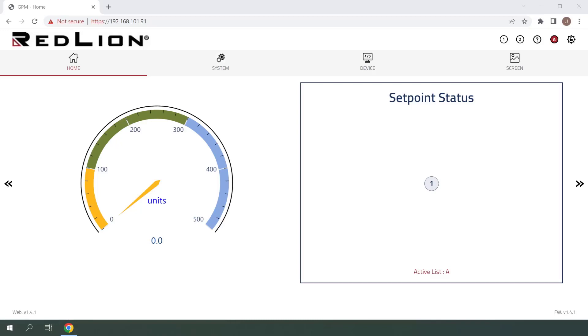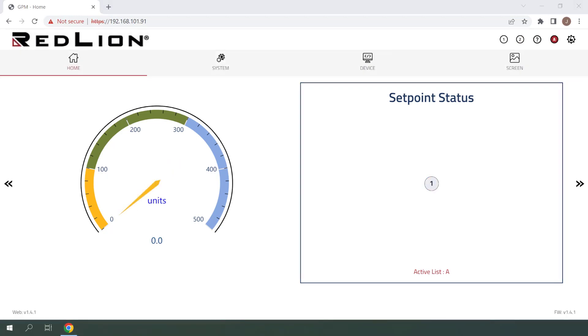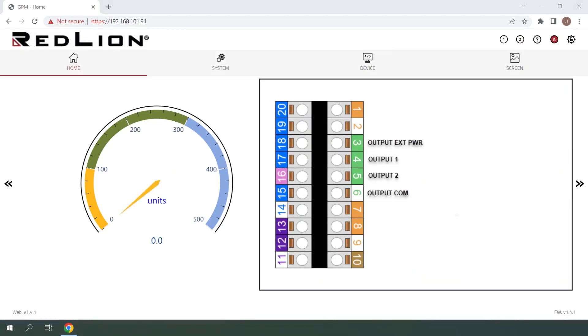The PM50 allows users to configure setpoint alarms to trigger when the measured input value falls outside of certain parameters, such as going above or below a setpoint value. When a setpoint alarm is triggered, the PM50 will display an enunciator banner by default to draw attention to the unit. Each setpoint also has a corresponding solid state relay output which closes when the alarm is active. For example, setpoint 1 controls output 1, and setpoint 2 controls output 2.